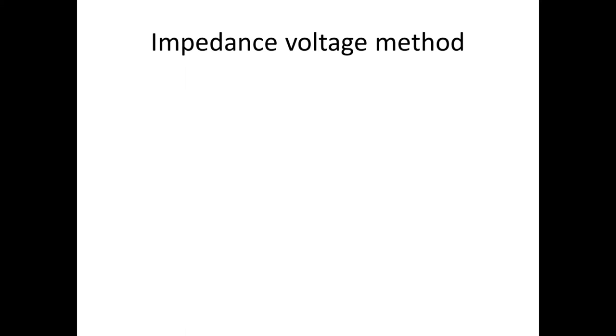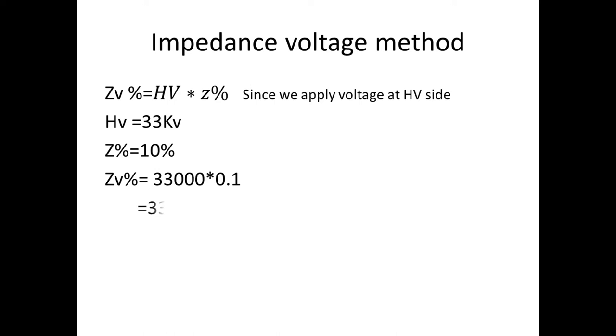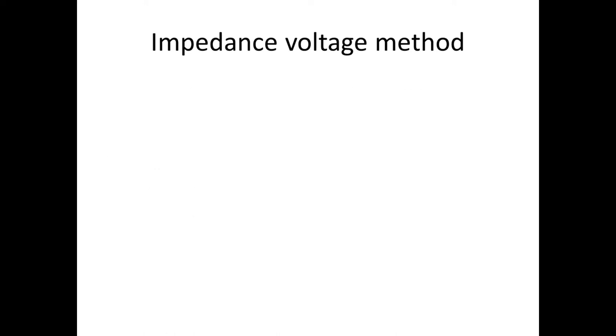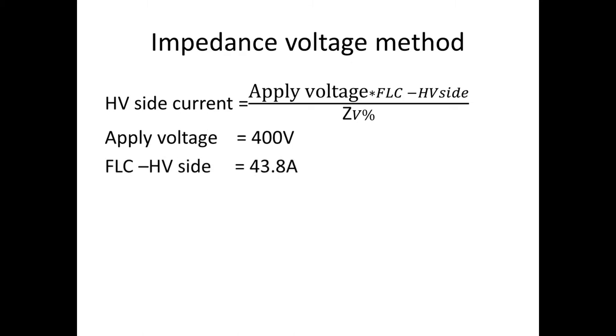Next, we apply the Impedance Voltage method. The formula is: Impedance Voltage = HV Voltage × Impedance Percentage. With HV voltage of 33 KV and impedance percentage of 10%, the impedance voltage is 3300 V. The HV side current formula is: (Apply Voltage × Full Load Current of HV side) / Impedance Voltage. Apply voltage is 400 V, full load current is 43.8 A, impedance voltage is 3300 V — giving 5.309 A.